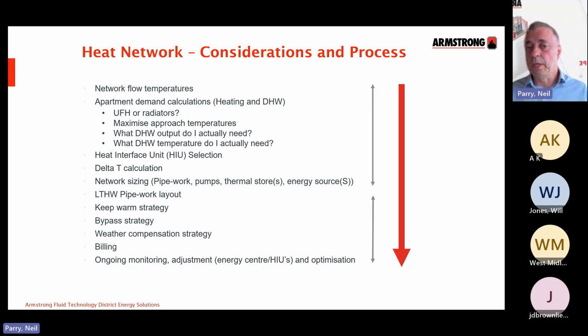Once you know what those demands are, you can then select the HIU to give you that performance. And only once you've selected the HIU do you then know what the delta T is going to be. The reason for that is quite simple. The delta T from the HIU when it's on domestic hot water demand is dictated by the length of the plate heat exchanger. Mainly, there are some other aspects that affect it, but it's mainly by exchanger length. And the longer the exchanger is, the lower the return temperature is. The shorter the exchanger, the higher the return.